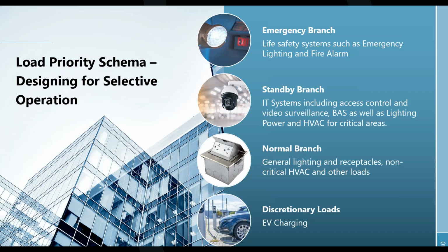You might have a certain room or portion of the building that's critical for the operation of the facility, and that would all go on the standby branch. The normal branch is the rest of your building, and discretionary loads are unique loads within the building that you may want to be able to turn off without disrupting building operations. A great example is EV charging, since we already talked about how huge of a load it is. For most buildings, those can go offline and barely impact the operation of the building. That's maybe not true for all projects, but for many, that would be an example of a discretionary load you want to be able to turn off if required.